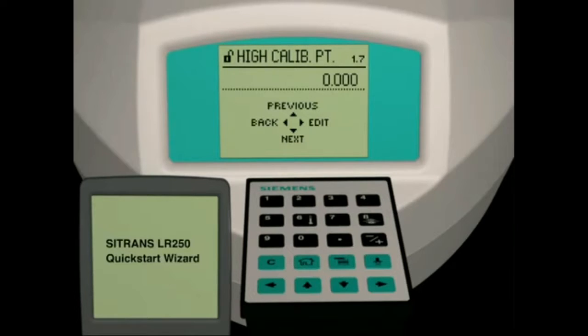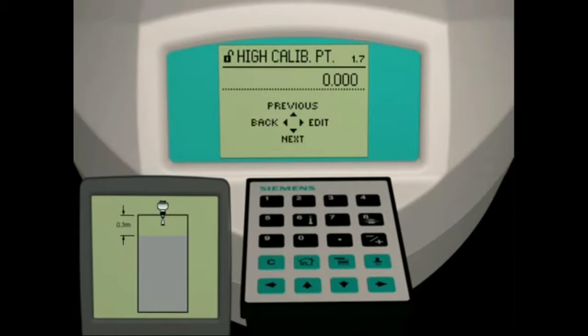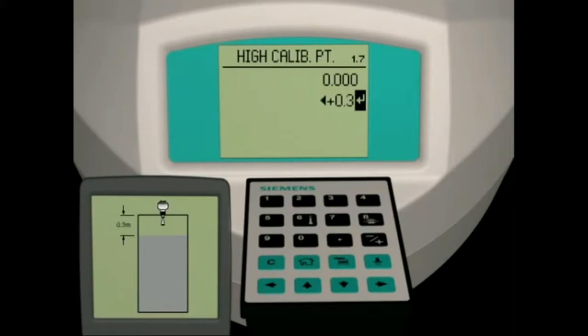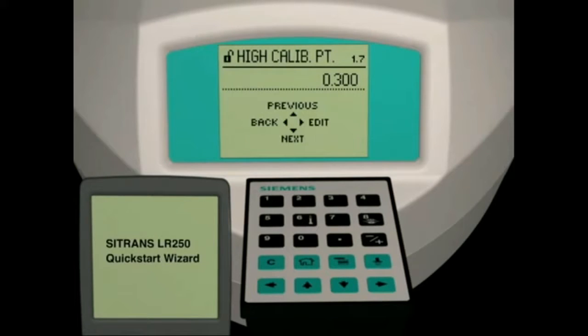Parameter 1.7 is the high calibration point. The high calibration point is the distance from the LR250 reference point to the highest level of liquid under normal operating conditions. In our application, this distance will be 0.3 meters. Press the right arrow key to enter parameter edit mode, then press 0.3. Press the right arrow key to set this value and to return to navigation mode.